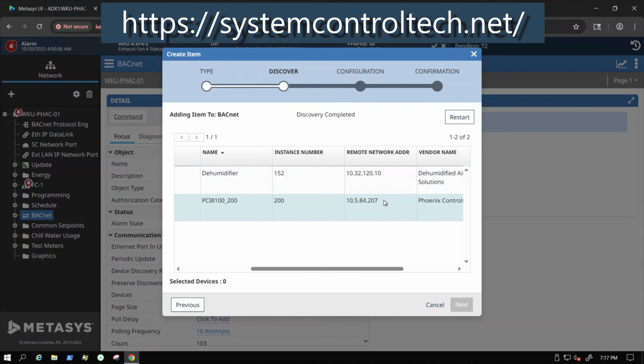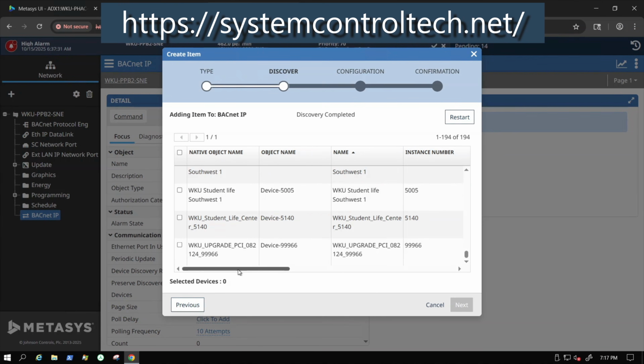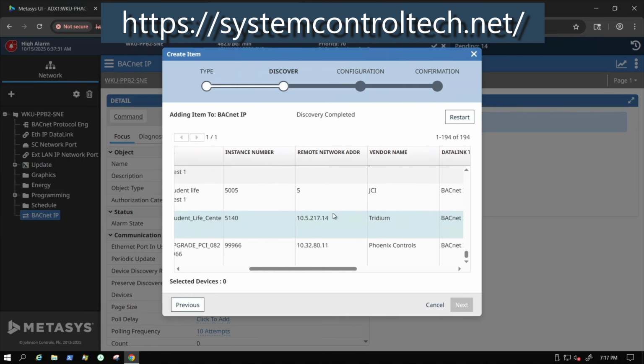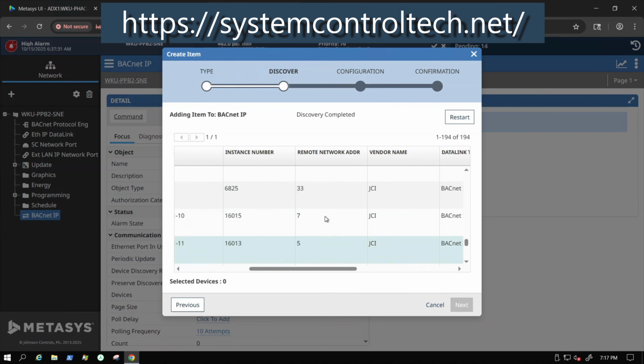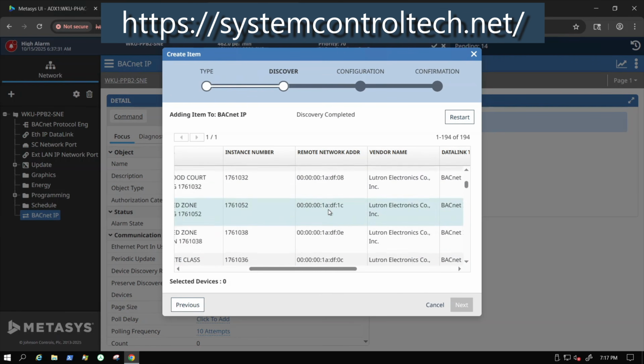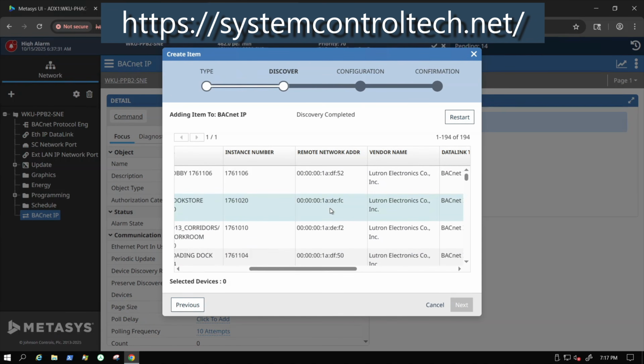I know this is not typically what I usually come up with on this. You know, there's some in-depth stuff, but if you're in there trying to get a device to communicate BACnet IP, and you're scratching your head, you cannot for the life of you figure it out, you might try this step. Change the IP address on that network engine and put it within the same range as that third-party device. Or you may try changing that third-party device to an IP address within the same range of your engine. And you guys know how this stuff is as far as your network engines and IP addresses, and it can get confusing.